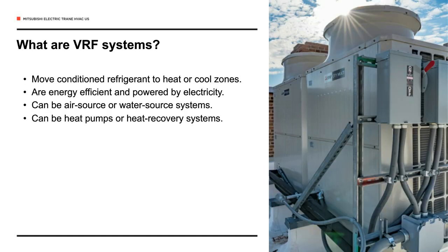I'd like to spend a little bit of time talking about what VRF systems are. VRF systems heat and cool zones by moving conditioned refrigerant through small diameter piping. VRF systems are electric powered and do not require fossil fuel combustion to generate heat. These can be heat pump or heat recovery systems. Heat pump systems are used for single zone applications or multi-zone applications that follow the same thermal profile. On the other hand, we typically install heat recovery VRF systems, which use a branch circuit or BC controller to provide simultaneous heating and cooling in multi-zone applications with diverse thermal footprints. For example, hotels, office buildings, and any facility where some zones will require heating while others require cooling, all in the same building.